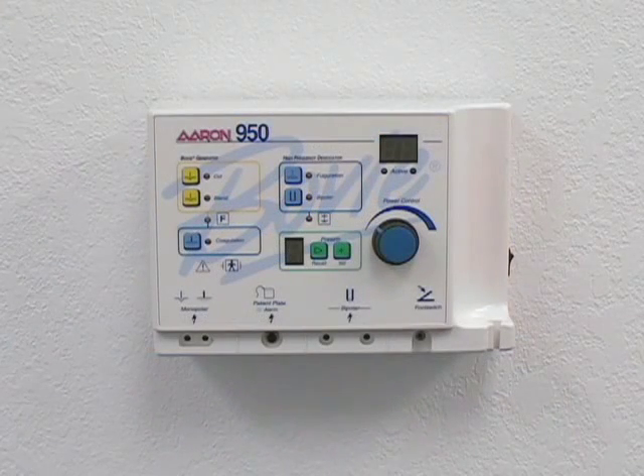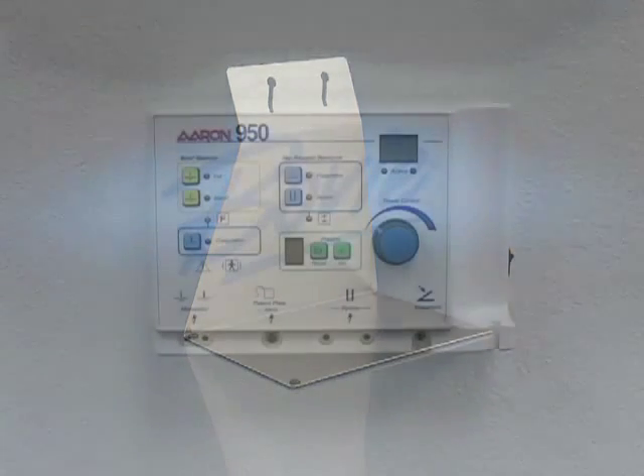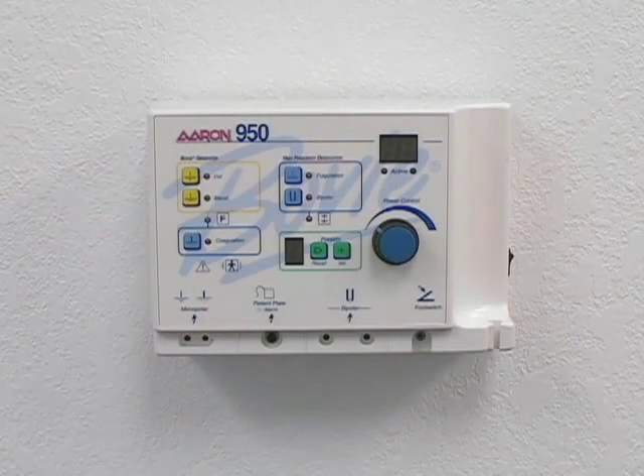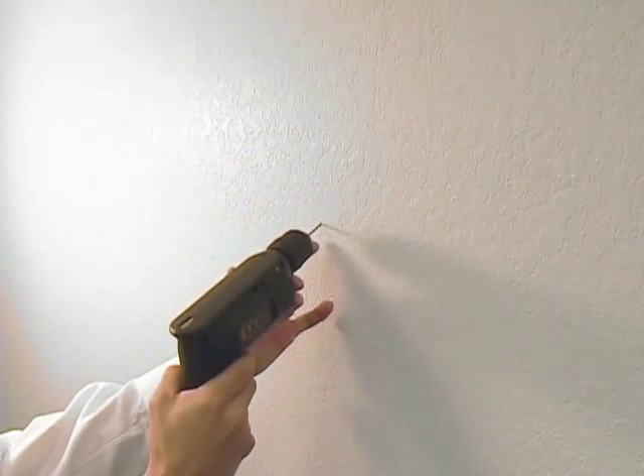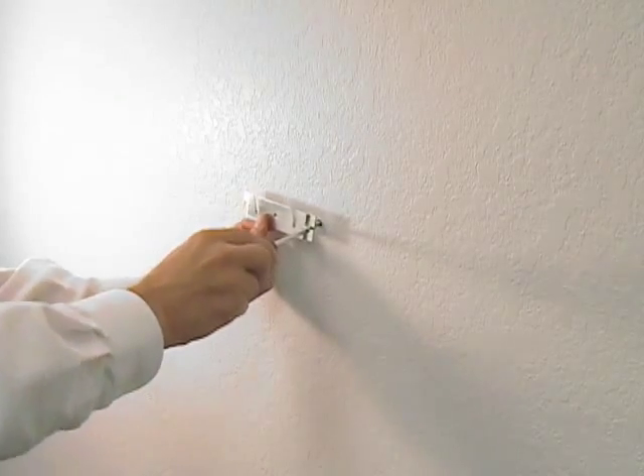The AARON 950 can be mounted on the wall, a mobile stand, or a tabletop stand. In order to mount the AARON 950 on the wall, use the following procedure: mark the drill holes using the bracket as a guide, drill out the holes using the 3/16 drill bit, seat the screw anchors into the holes, insert the screws through the bracket into the anchors, then slide the mounting screws into the grooves on the bracket.